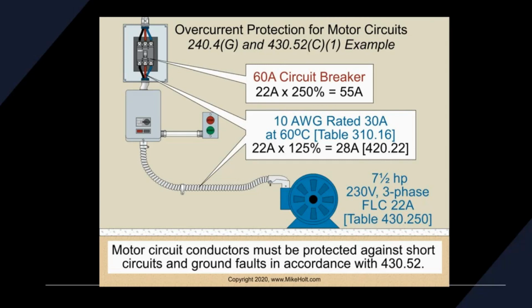Just one more here. We can clean this up a little bit. So you can see where we're at here. We're taking the FLC, multiplying it by 125% to get an amperage. And then we're going to the appropriate table. If they're asking for SO cord, we're going to go to the table for SO cord. If they're asking for a normal conductor, we go to 310.16. It's really just that easy.